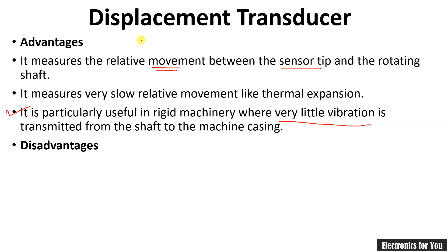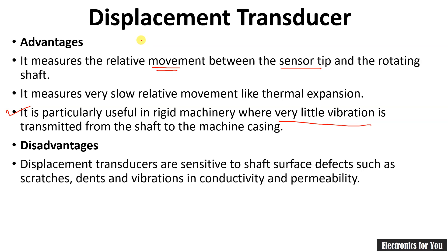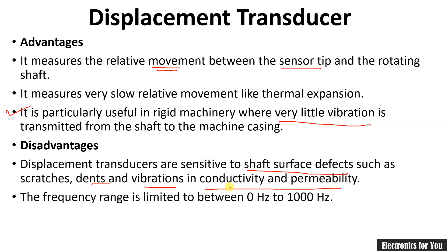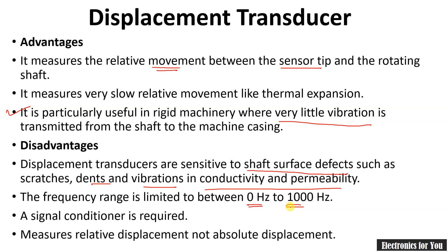The disadvantages of displacement transducer: they are sensitive to shaft surface defects such as scratches, dents, and variation in conductivity and permeability. The frequency range is limited from 0 hertz to 1000 hertz. A signal conditioner is required in the case of a displacement transducer. It measures relative displacement and not absolute displacement.